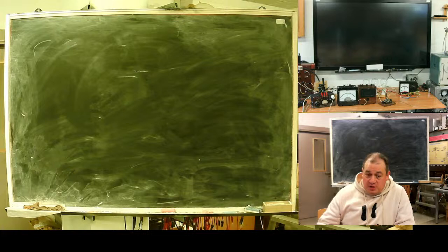And it is better to measure after assembly, because for this dissipated magnetic flux, all kinds of covers, shroud, supports, cooling, even the cooling pipeline may change the distribution of magnetic field and resulting resistance. No way to get good data.